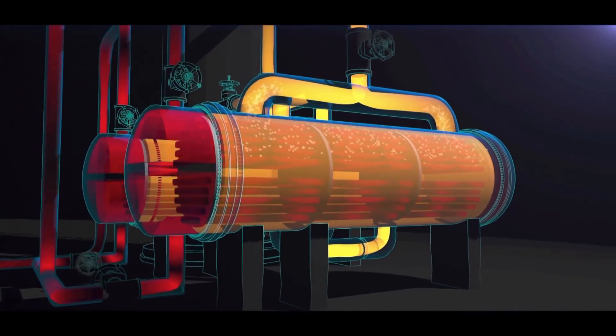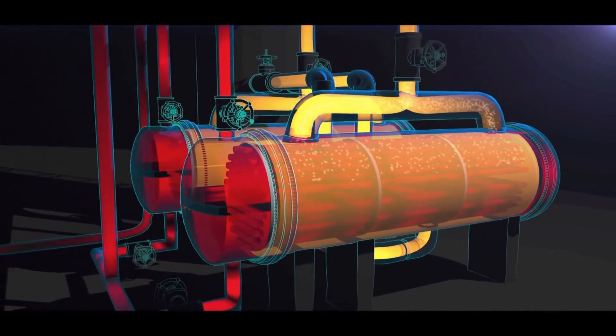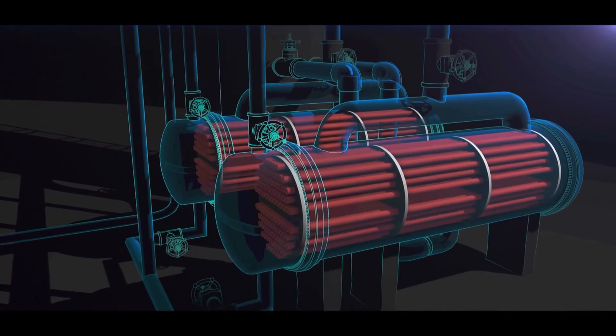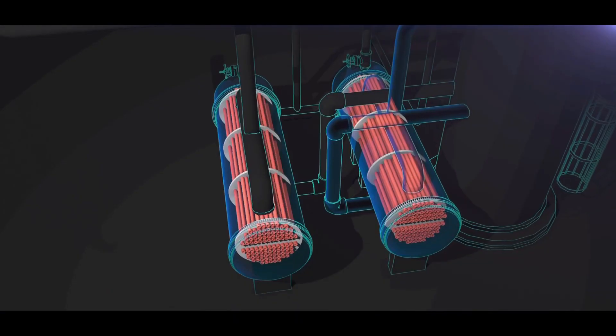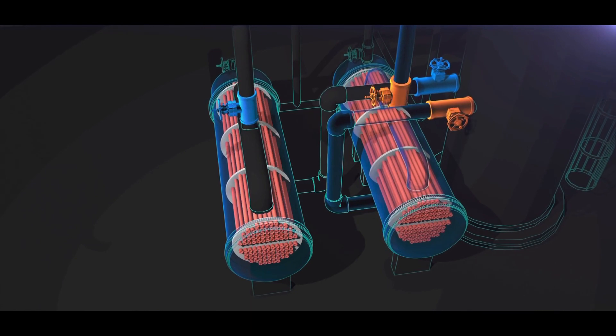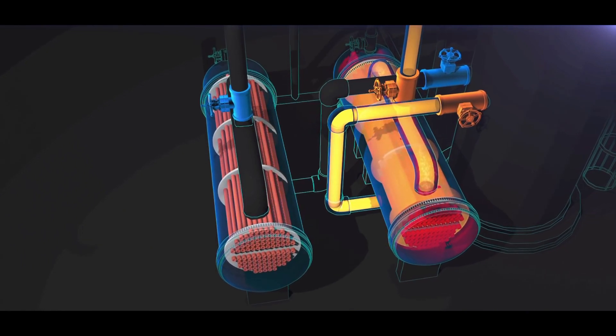The original propylene fractionator design had both reboilers running simultaneously. But in that configuration, the fractionator had to be shut down when a reboiler fouled and needed cleaning. To prevent shutdown of the propylene fractionator each time the reboilers needed to be cleaned, in 2001 new valves were installed on each reboiler to allow for operation of only one at a time. The other reboiler is on standby, clean and ready for use.